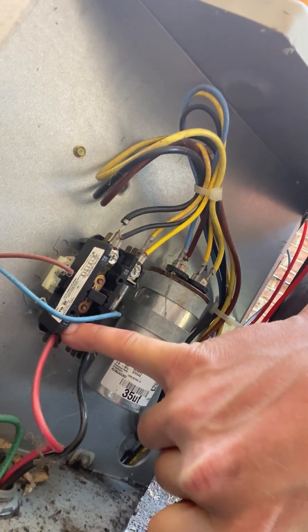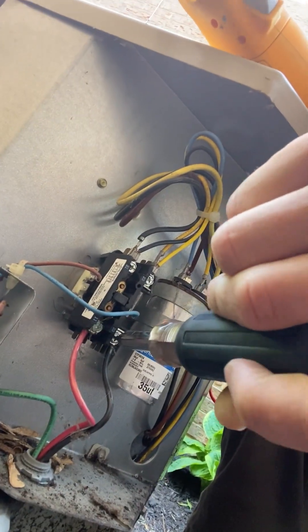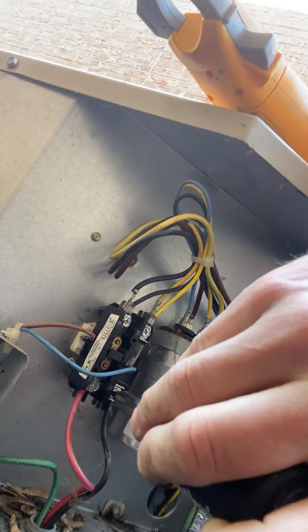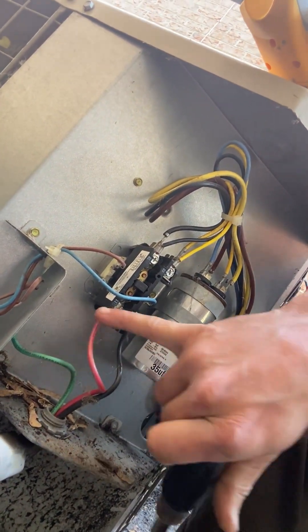I just checked this one — it's quite loose. Let's see what we got here. Barely tight as well. Those loose connections can generate heat. That heat's going to break down the plastic that's around here, going to deteriorate this wire, and eventually lead to a failure.